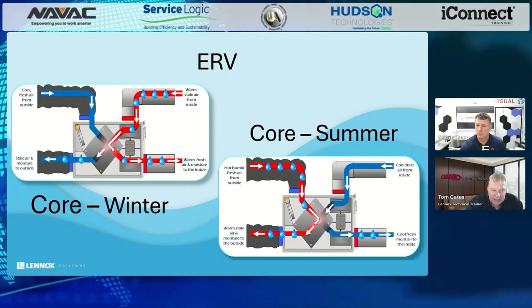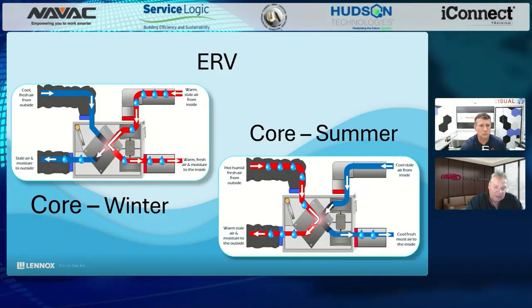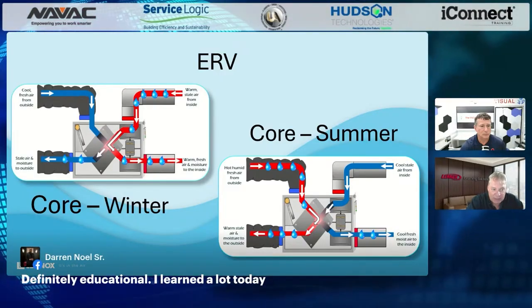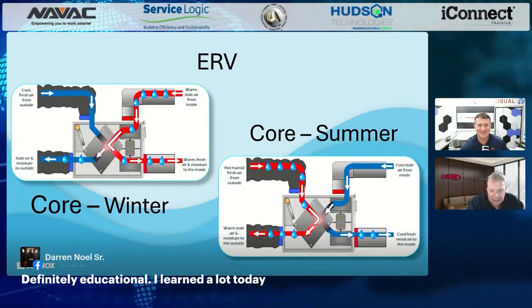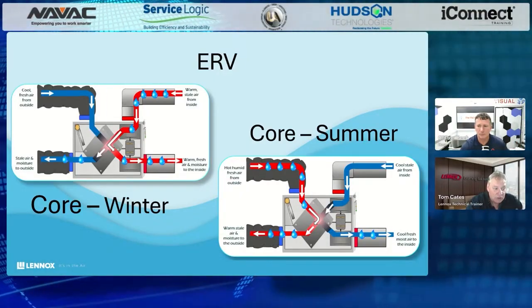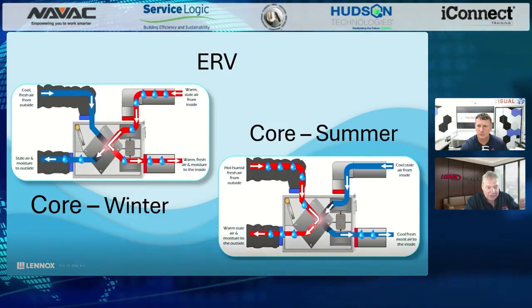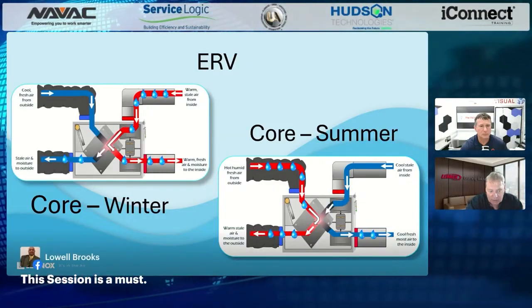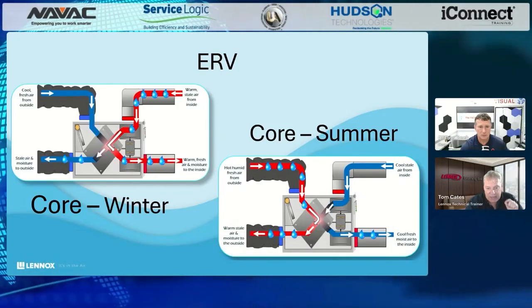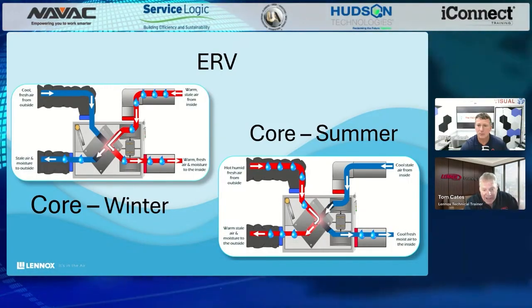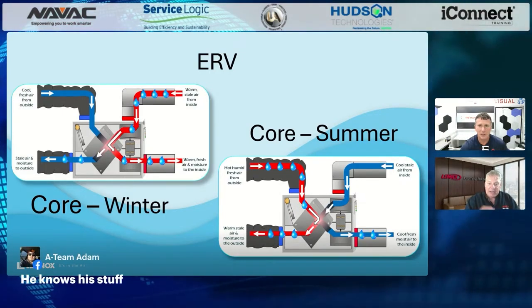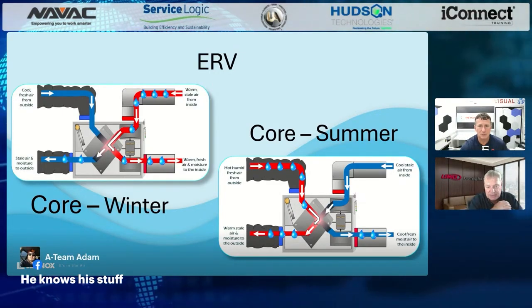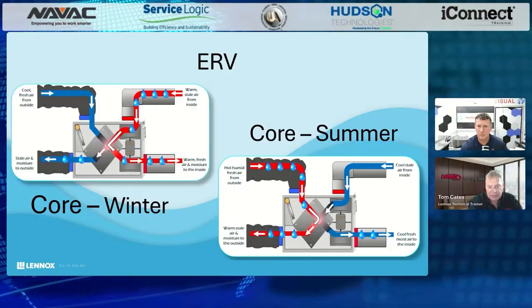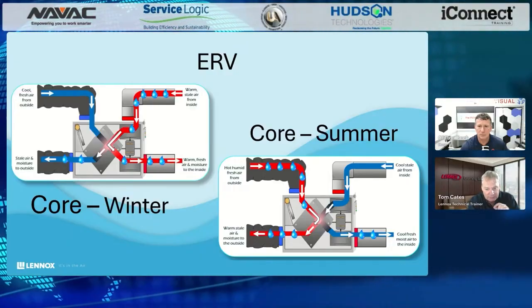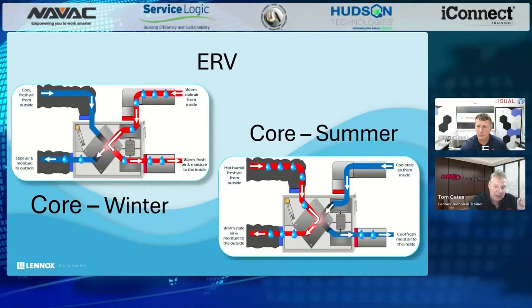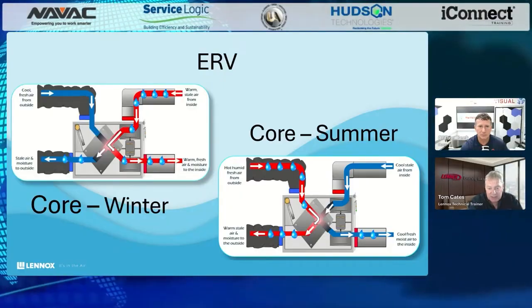With an ERV, in this example in winter, I've got 5 grains of moisture leaving the house. That's the water droplets. 2 of those grains will move to the outdoors, but 3 will stay indoors. That's where we get the ability to not entirely dry out the air, but manage it better. It returns moisture so it doesn't dry the air out, managing it more appropriately. So I can have higher ventilation rates without reducing the amount of moisture in the air.